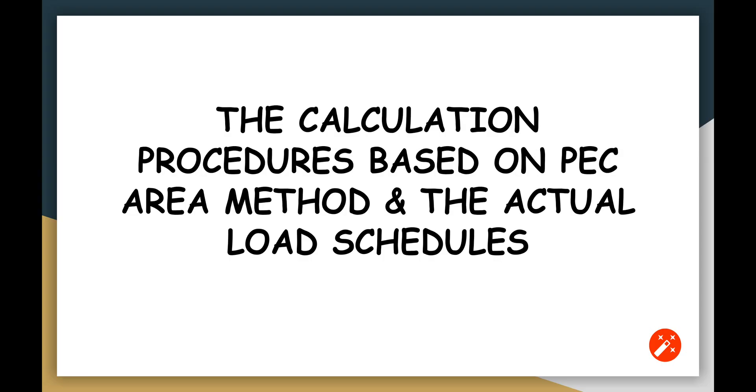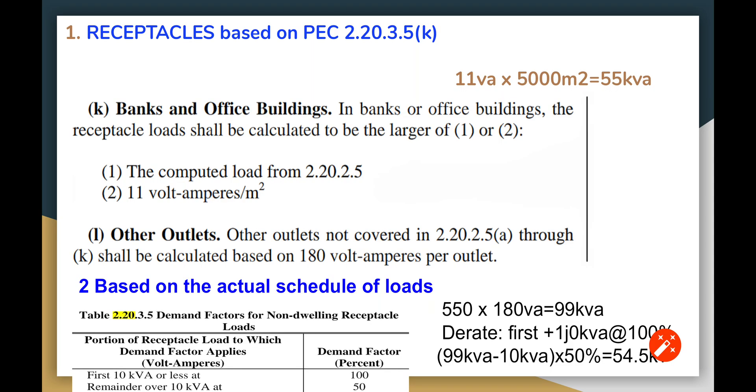Let's go for the calculation procedures. First is the receptacles, and based on the PEC we have 11 volt amperes per meter squared, and we're going to multiply that by the square area and we're going to get 55 kVA. If you're going to use the schedule loads, we have 550 receptacles times 180 VA, and that VA is going to give us 99 kVA.